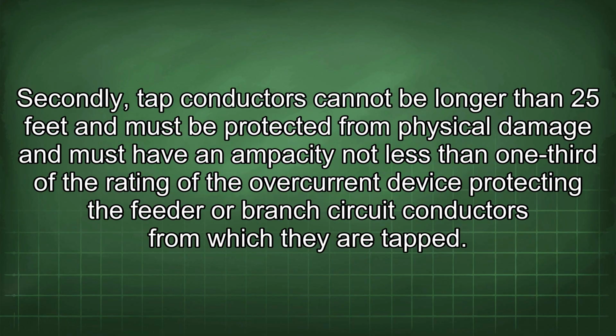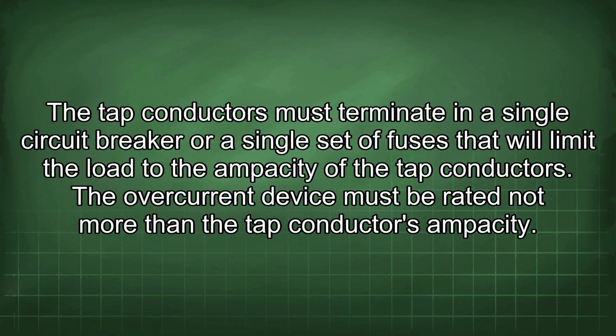Secondly, tap conductors cannot be longer than 25 feet and must be protected from physical damage and must have an ampacity not less than 1/3 of the rating of the overcurrent device protecting the feeder or branch circuit conductors from which they are tapped. The tap conductors must terminate in a single circuit breaker or a single set of fuses that will limit the load to the ampacity of the tap conductors. The overcurrent device must be rated not more than the tap conductor's ampacity.